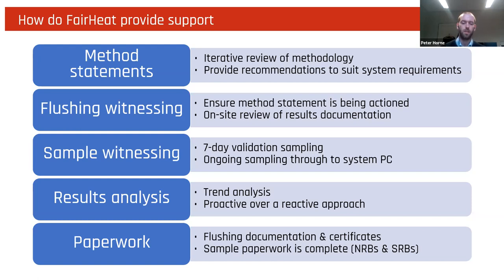We do go on site to witness that, and also witness sampling in line with British standards is what we're looking for. And within that method statement, we are looking to get the results of those samples in line with the target acceptable limits that have been defined in the method statement. Throughout ongoing sampling, we're looking for trend analysis. That's to maintain a proactive approach over a reactive approach. And we really want to make sure that any issues that do come from the samples are dealt with before they become a major issue.